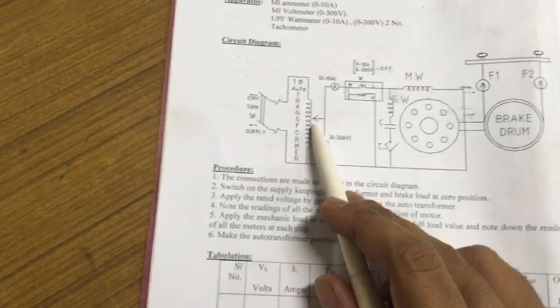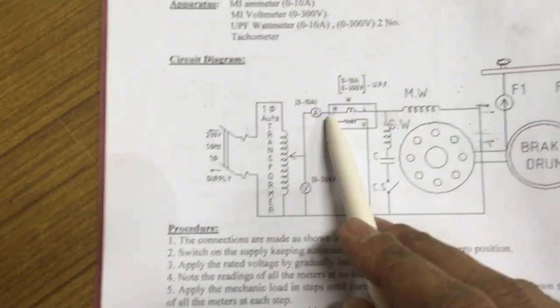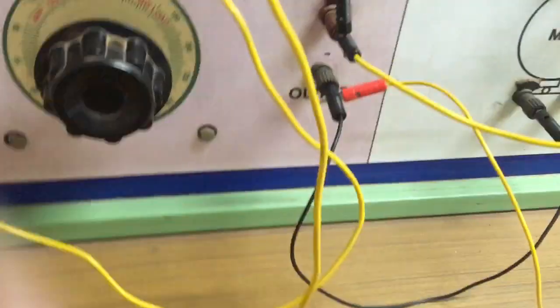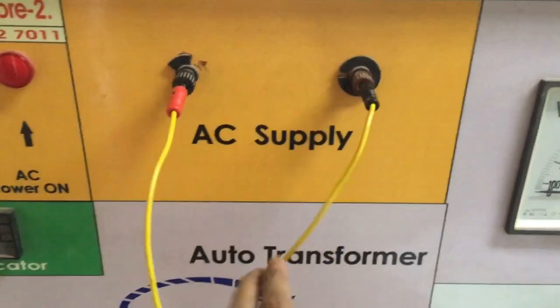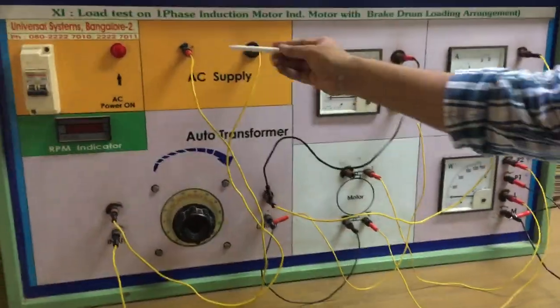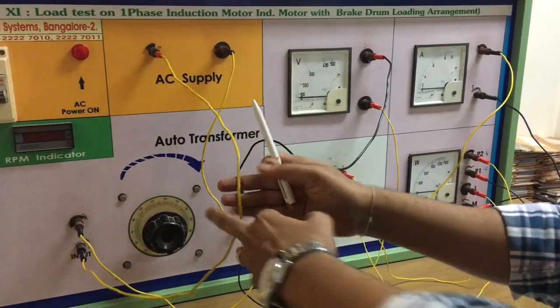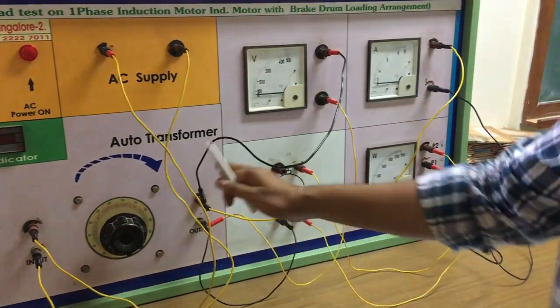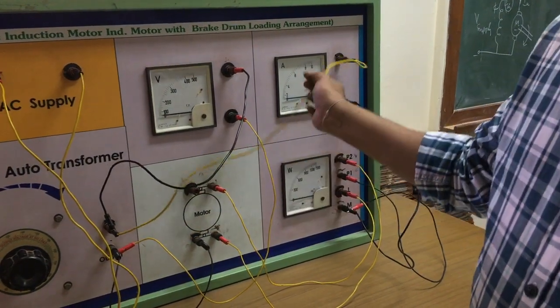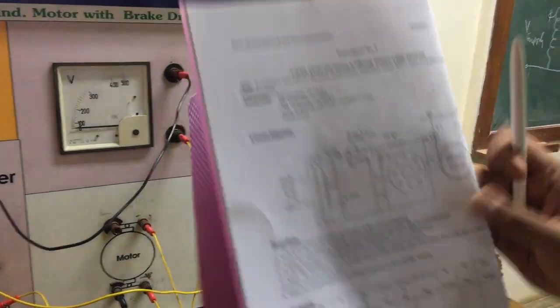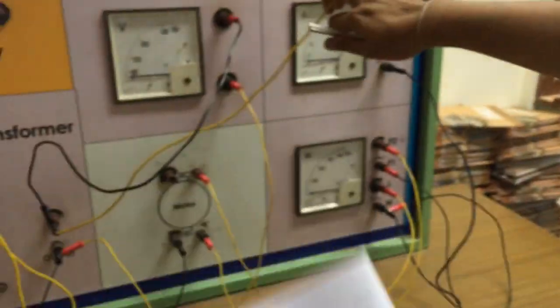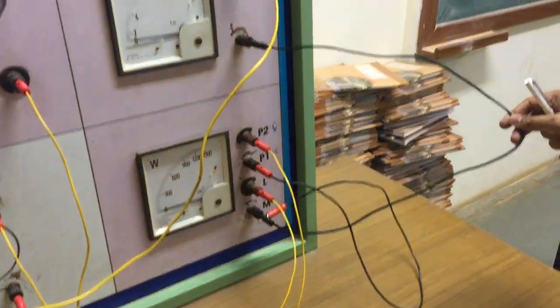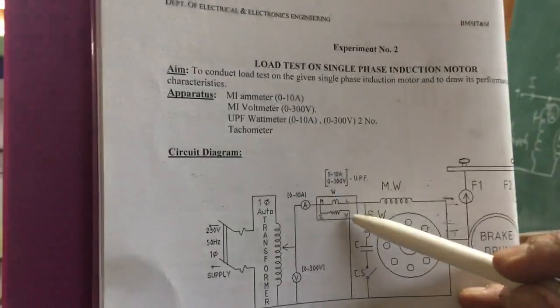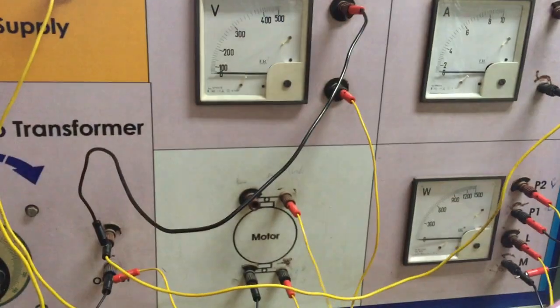The connections are from the auto transformer terminal to the ammeter, and from the ammeter to the mains of the wattmeter. The auto transformer is supplied from the mains. This is the main supply terminal. From the supply terminals I am giving to the input of the auto transformer. The output of the auto transformer is connected to the entire circuit. One terminal of the output of the auto transformer is connected to the ammeter. Then the ammeter is connected to the mains of the wattmeter. Then the line of the wattmeter is connected to the motor.